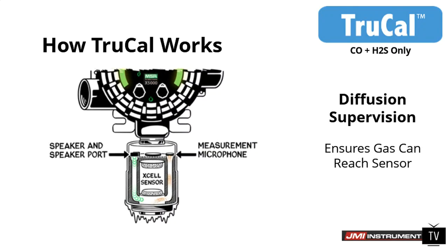So the other half of why we did a calibration was to ensure gas is reaching the sensor. Well, now to incorporate this whole TruCal function, we have something called diffusion supervision, where we're monitoring a sound wave within the sensor to ensure that the gas can reach the sensor itself.